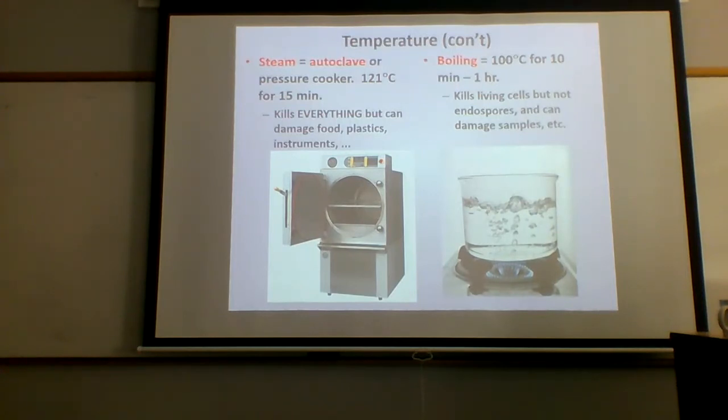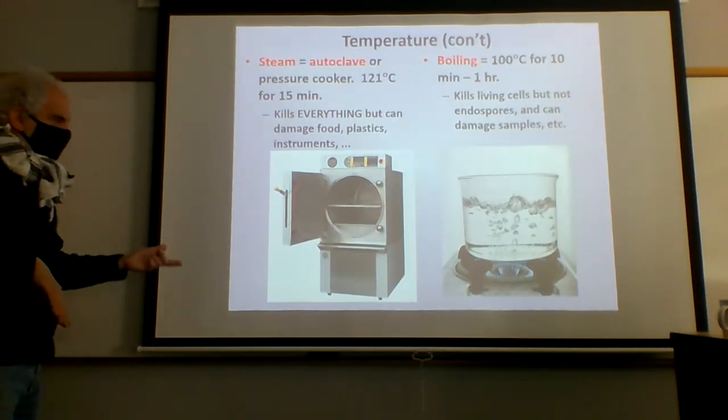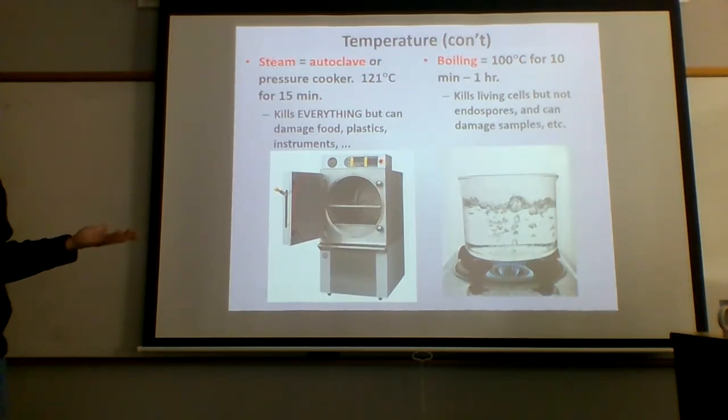Just remember that water would typically boil at 100 degrees. So you've got a fair amount of pressure in here. The standard way to do this is to have a steam autoclave. There are other ways you could do it, but a real easy way is you put a big bucket of water in the bottom of a pressure vessel that you can heat up. You turn the heat on, which is what ours do, we have big electric heaters, and the water begins to boil. The samples aren't yet at that temperature.